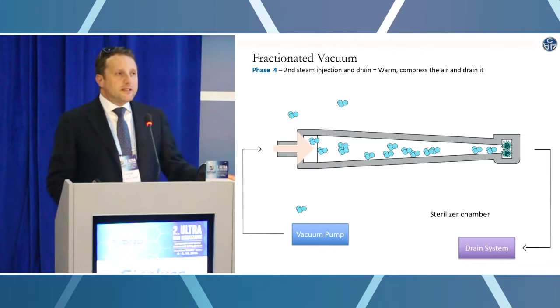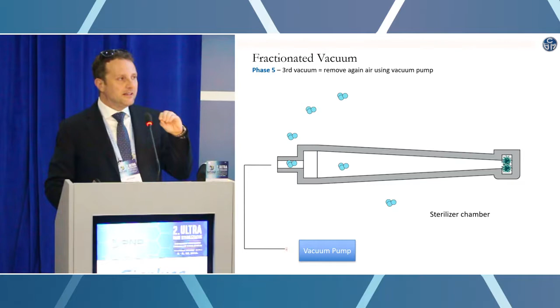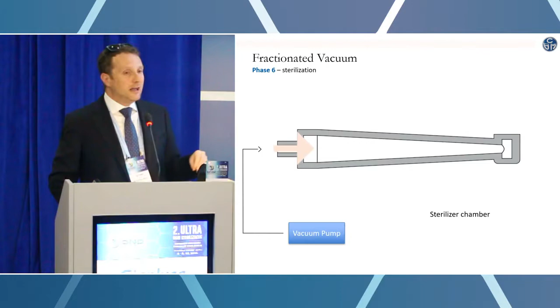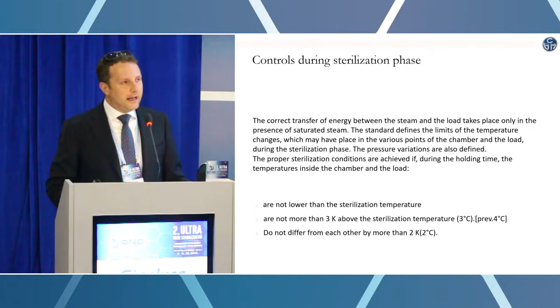This morning we also saw what saturated steam means. So it's quite difficult to maintain the correct steam condition to have correct steam sterilization. A brand new steam sterilizer, according to EN 13060, should be able to evaluate itself on whether the sterilization performance was correct. In other words, at the end of the cycle, the sterilizer must give you an indication if saturated steam was present or not inside the sterilization chamber.